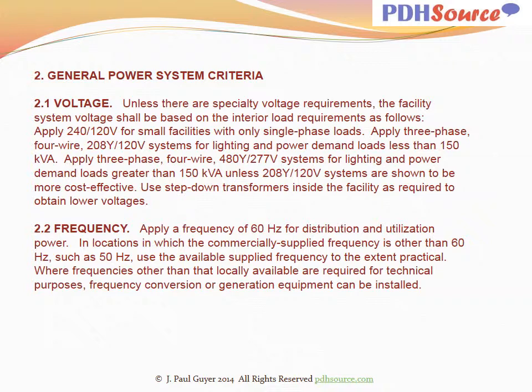Some comments on general power system criteria, the voltage. Unless there are specialty voltage requirements, the facility system voltage shall be based on the interior load requirements as follows. Apply 240-120 volt for small facilities with only single phase loads. Apply three phase four wire 208Y-120V systems for lighting and power demand loads less than 150 kVA. Apply three-phase four-wire 480Y-277 volt systems for lighting and power demand loads greater than 150 kVA, unless 208Y-120 volt systems are shown to be more cost-effective. Use step-down transformers inside the facility as required to obtain lower voltages.